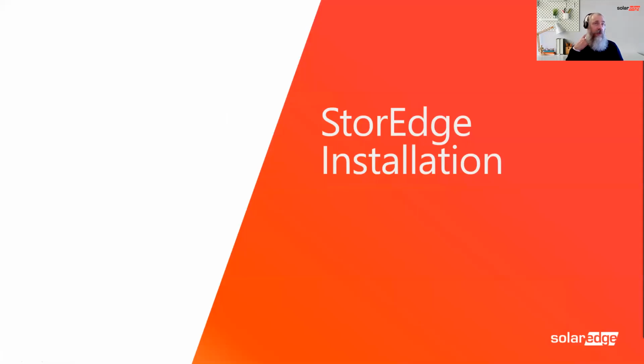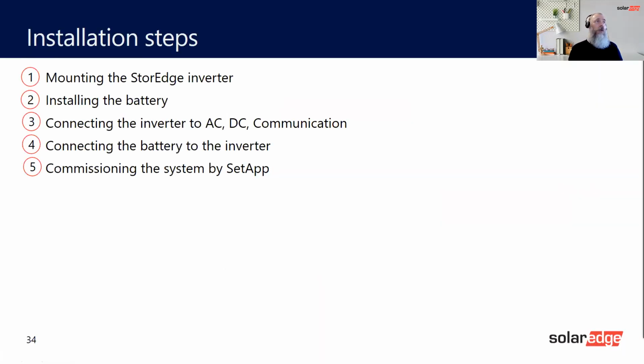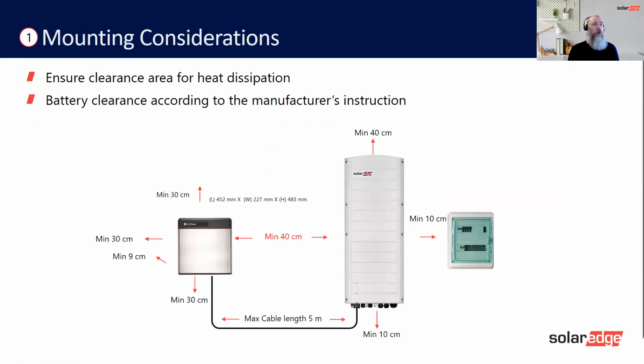So the installation of the product, we're going to look at mounting the inverter, installing the battery, connecting the inverter, connecting the battery to the inverter, and commissioning by SetApp. So there's a couple of rules here. The first one is clearance, simply because the inverter needs to dissipate its heat. You can see on here, there should be exactly the same as what you're familiar with, 40 centimeters on top, 10 centimeters to the side and 10 to the bottom.